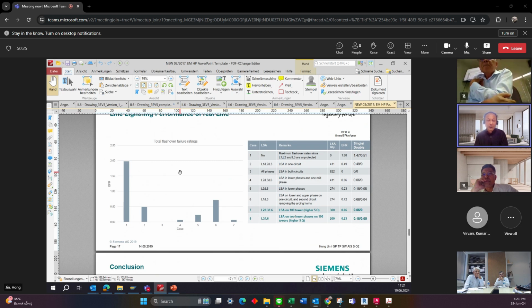As an example, I just share with you, we have also a project in Australia, roughly 600 kilometers long, at 500 kV. They want to install 500 kV EGLA, 6,000 pieces. They made the budget because of a very bad geography situation. In this area they have very rocky soil and a very high footing resistance. So if you install the EGLA on the towers, then you don't need to reduce the footing resistance. You can save a lot of workload and money, because if you install the surge arrestor on the towers, the flashover will be protected by the surge arrestor itself.